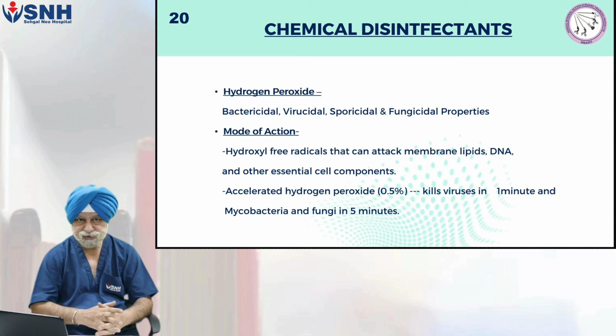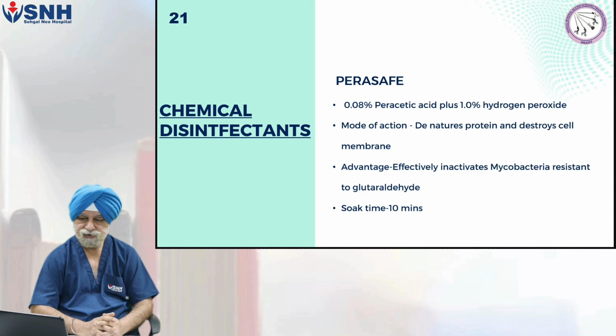The other chemical that we use is Perasafe. This is 0.08% peracetic acid plus 1% hydrogen peroxide, and the mode of action is that it denatures the proteins and destroys the cell membrane. The advantage is that this effectively inactivates the mycobacteria which are resistant to the glutaraldehyde. The soak time, or contact time, for high level disinfection is 10 minutes. This Perasafe is costlier than the glutaraldehyde and the Cidex.